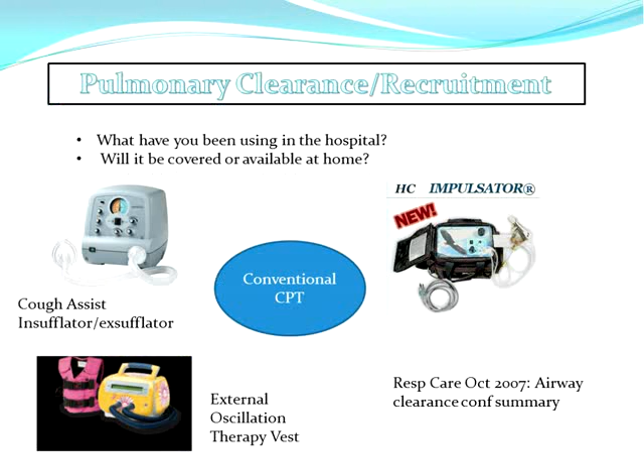What about humidification? So typically in our critical care environments, high-end critical care environments, we're using at least some traditional active humidity. Ideally, these traditional active humidity devices are going to be providing 44 milligrams of water per liter at body temperature and saturation.